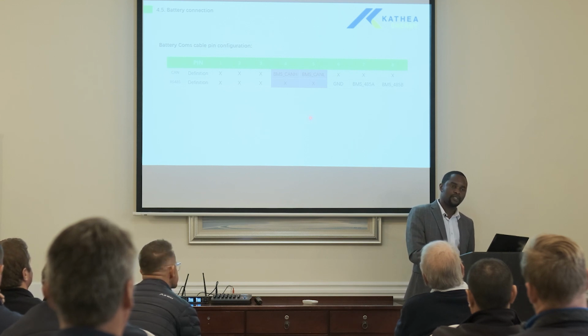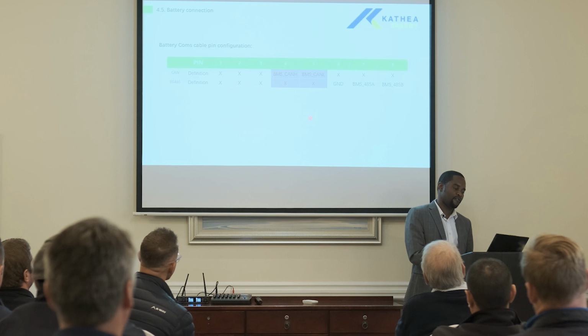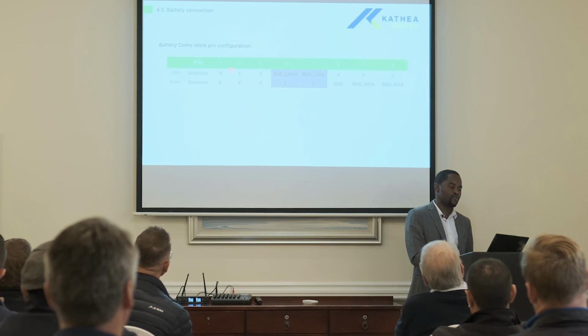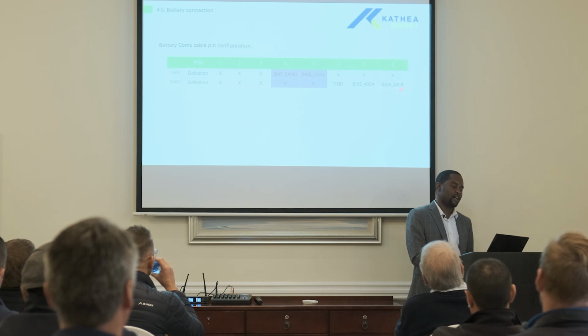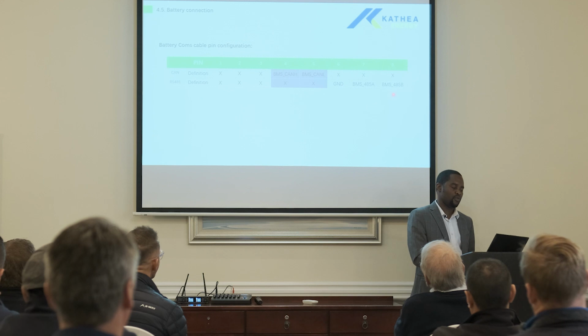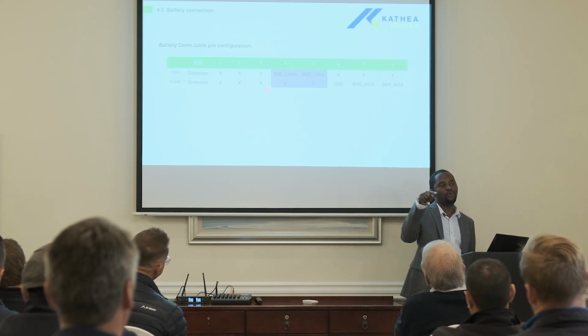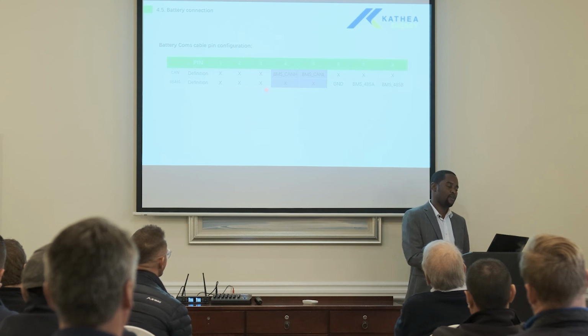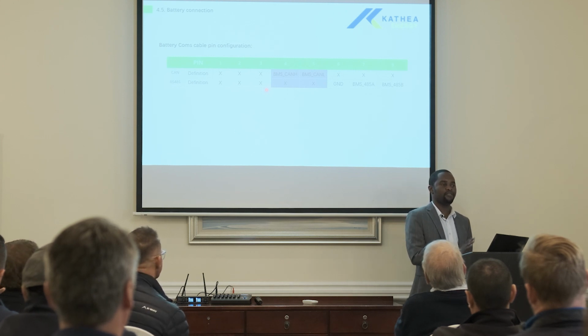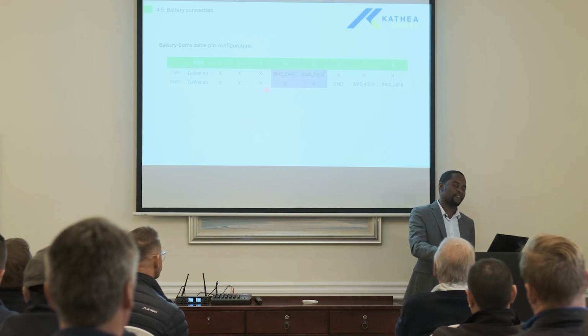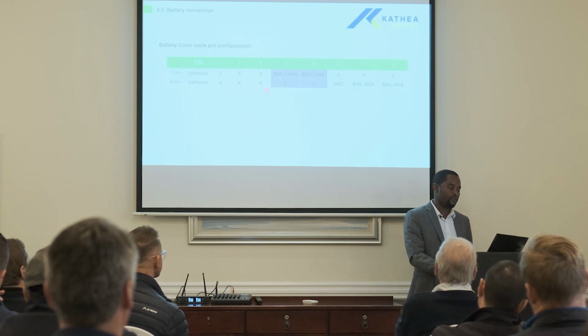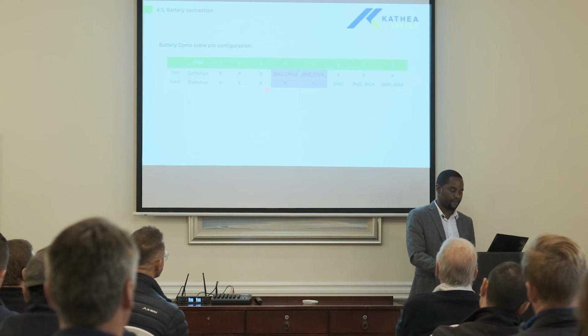It also supports, the BMS supports RS-485. If you've got RS-485, you can use pin 1 and 2 or pin 7 and 8. So these are RS-485 pins. 7 and 8 is demarcated, 1 and 2 they put X's, but it's both. You've got redundancy in terms of RS-485 because you may actually need to loop or parallel the BMSs. But for now, you don't need to parallel the BMSs even if you've got 3 inverters in parallel. You just wire everything on your master inverter. Then the master inverter will convey that information to the slaves.